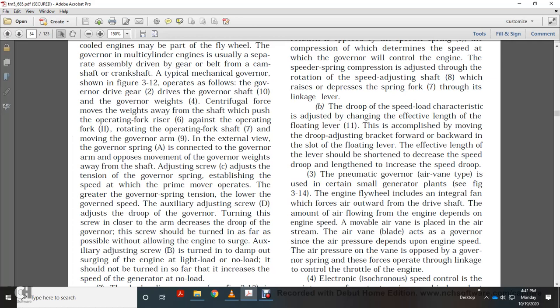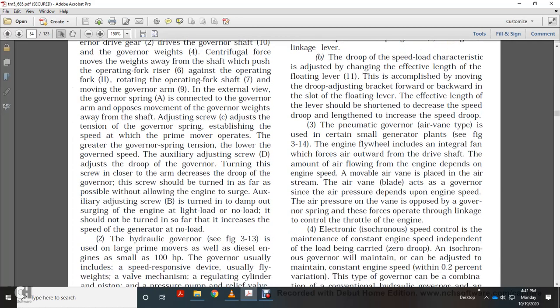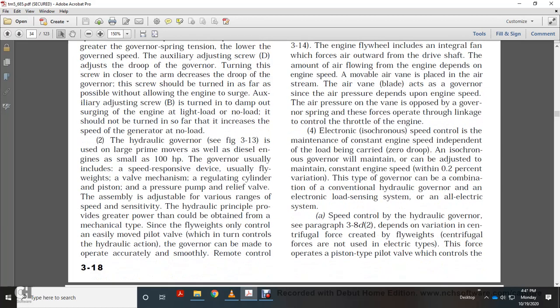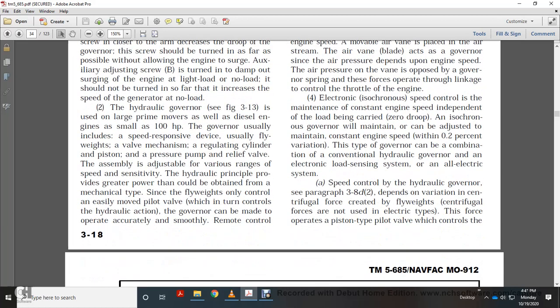The auxiliary adjusting screw is turned to damp out engine surging at light load or no load. It should not be turned in so far that it increases the speed of the generator at no load. The hydraulic governor is usually used with large prime movers — diesel engines as small as 100 horsepower. It includes speed-responsive flyweights, a valve mechanism, a regulating cylinder and piston, a pressure pump with relief valve, and adjustable speed sensitivity. Hydraulic principles provide greater power than the mechanical type, since flyweights only control the easily moved pilot valve, which in turn controls the hydraulic action.